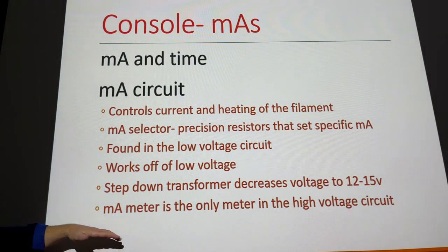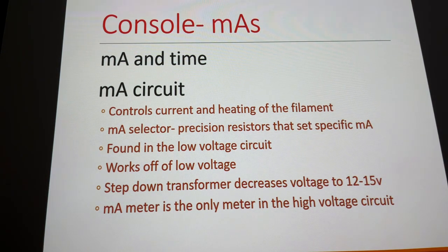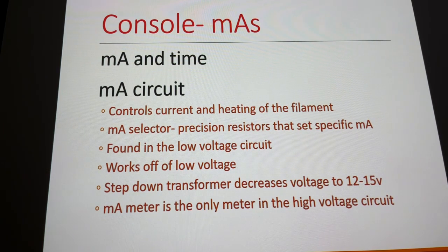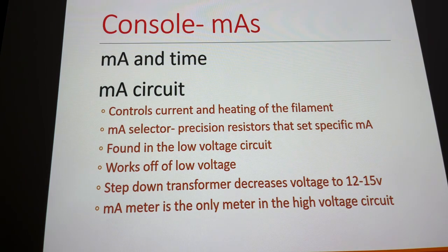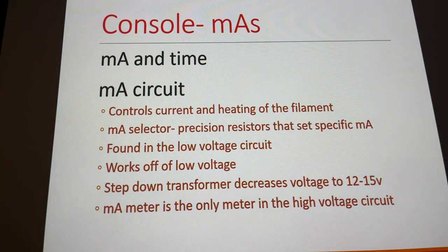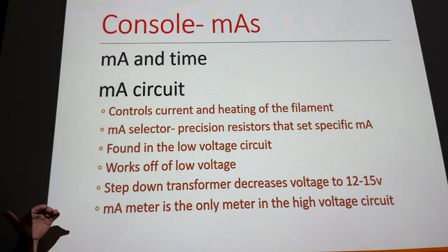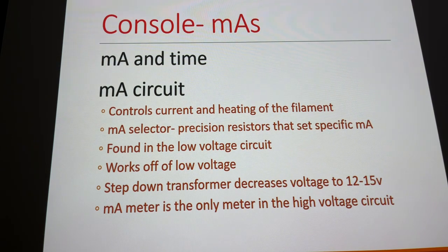All gauges and controls on the control panel work off low voltage for safety. You'd expect all of them to be in the low-voltage circuit, but the MA meter is actually in the high-voltage circuit — wired into the dead center of the high-voltage transformer. At that center point, voltage is essentially zero volts, so it still works off low voltage, but it's located in the high-voltage circuit.